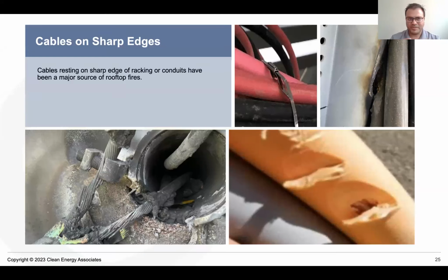If you think about it, there's thermal cycling, as temperatures change every day, night, and season. This thermal cycling causes expansion and contraction of the cables. When cables sit on sharp edges, they rub against them and damage the insulation. This is a major issue, and we've noticed a lot of thermal events caused exactly by this.